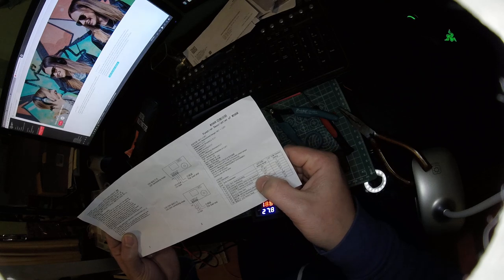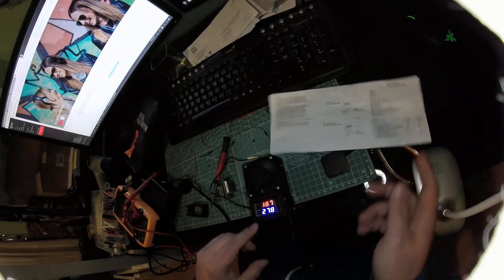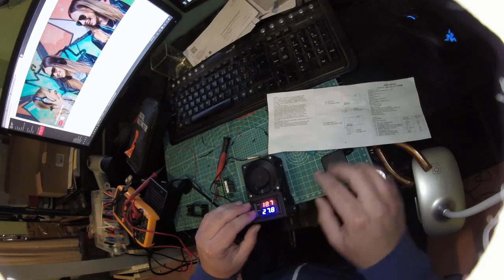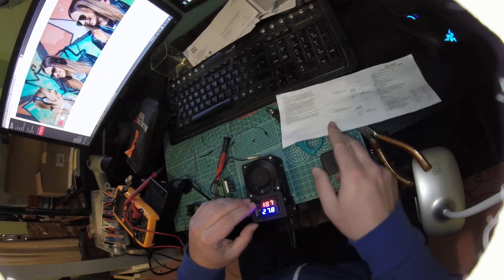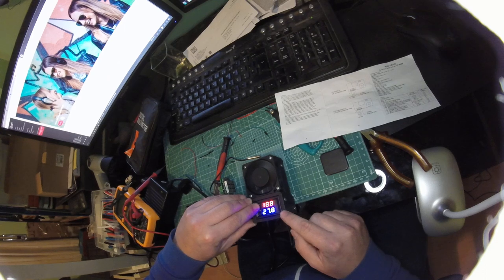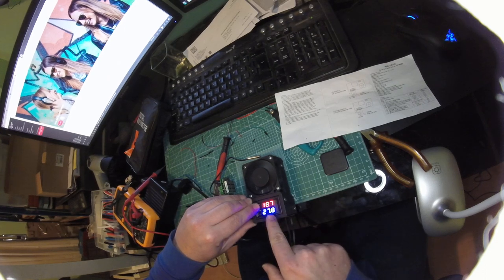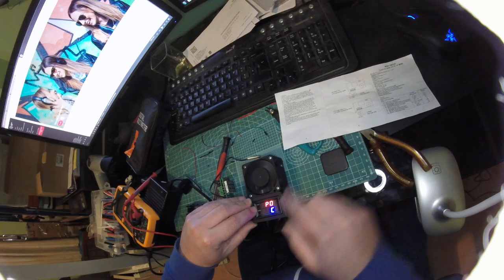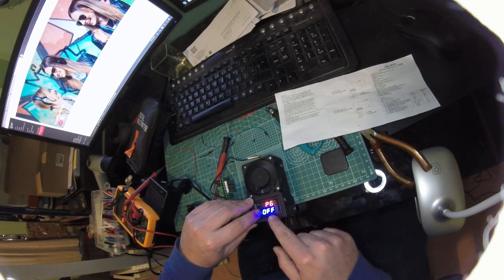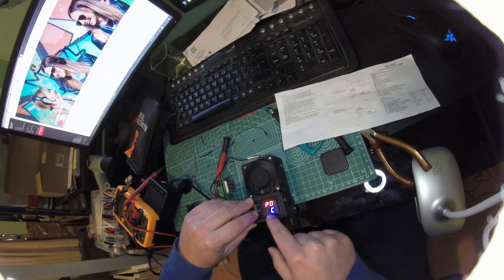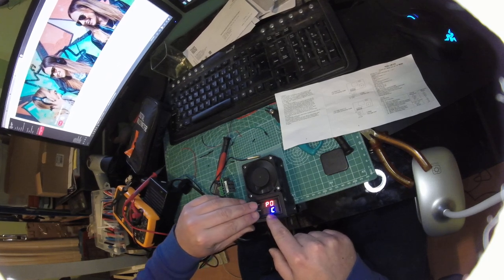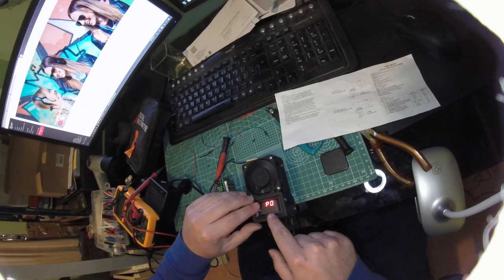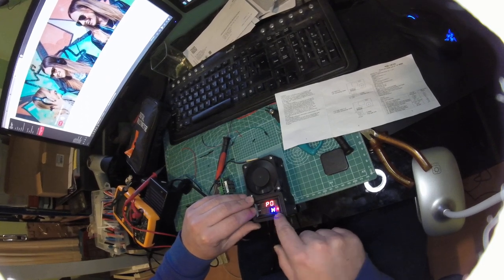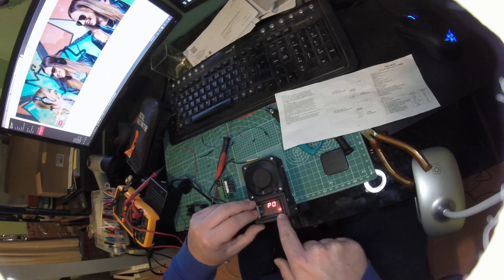So what we have to do is turn this into heat. To enter the setup menu, you press set for 5 seconds, and it will change to P, which is a program. Here you can cycle the various programs, and in this case we want to set P0 to heating instead of cooling. You have to press 2 buttons to enter the programming mode. Select the heating, and now you can see the red light is on, it's heating now.